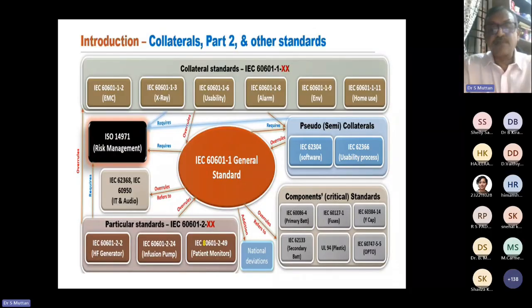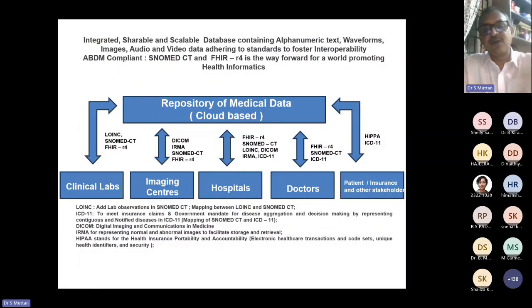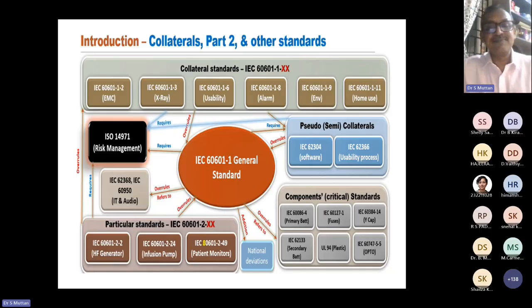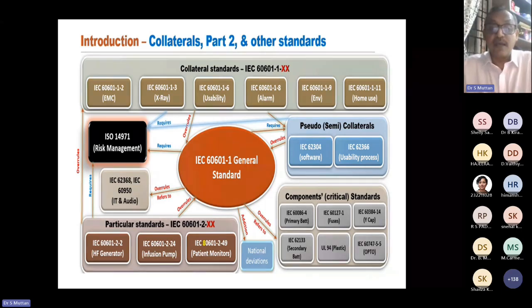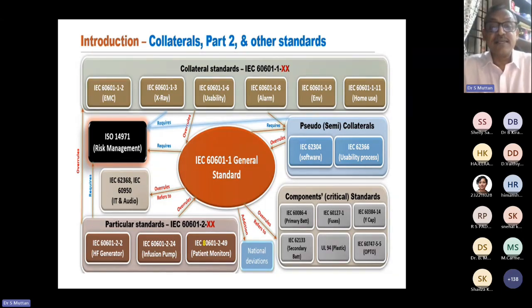So that is one kind of standard. This is completely software. Whatever I have shown here, 95% of them are software standards. This is for hardware, IEC 60601. Whenever you make a medical device, then people will say, is your medical device in compliance with IEC 60601, which is called the general standard? Is it satisfying collateral standards, which is called IEC 60601-1-X, which means 2 stands for electromagnetic compatibility, 3 stands for X-ray, 6 stands for usability, 8 stands for alarm. That is, whenever you design any medical device with some alarm, then they will ask whether we have satisfied 60601-1-8.